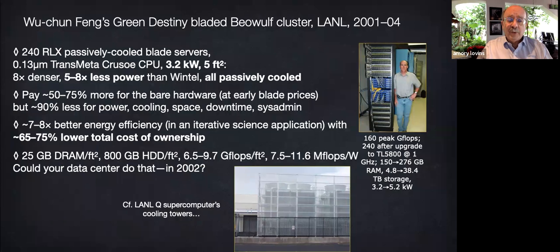And this design also offers design lessons about reliability. That is, the tortoise can beat the hare. If mean time between failures is shorter than computation time, Green Destiny at the upper right beats Q, just as a Camry eventually beats a blazingly fast but unreliable Formula One car. The actual mean time between failures is often set, you see, not by hardware, but by software bugs, by human error in integration, installation, configuration, operation, repair, upgrade, and so on. Also, 10°C cooler operation typically doubles equipment life.